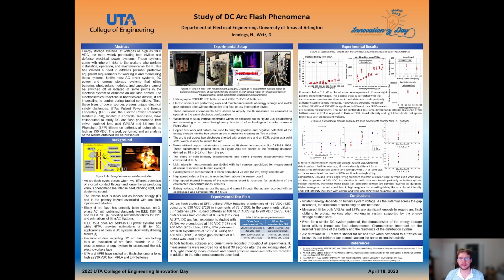Looking at the arc duration, we can see this is correlated as well too with the EPRI data. UTA data shows that no matter what correlation or series string combination we're using, it does linearly increase, with the highest durations measured in the lowest string count. For EPRI, using their lowest string count, we see that they're much lower than UTA's highest string count of 16P. This primarily is associated with their lower arc flash incident energy. Of the light intensity studied by UTA and at our facilities, we noticed that with higher string count, we saw greater light intensity and sound intensity. We believe this is due and mostly associated with the higher current produced in each arc.